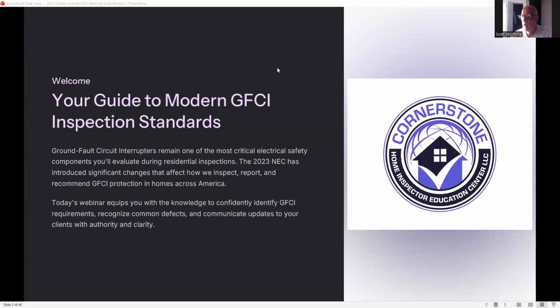So, your guide to modern GFCI inspection standards. Ground fault circuit interrupters remain one of the most critical electrical safety components you'll evaluate during residential inspections. The 2023 NEC has introduced significant changes that affect how we inspect, report, and recommend GFCI protection in homes across America. Today's webinar equips you with the knowledge to confidently identify GFCI requirements, recognize common defects, and communicate updates to your clients with authority and clarity.